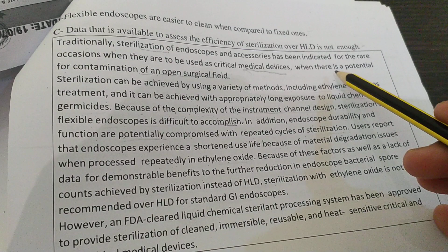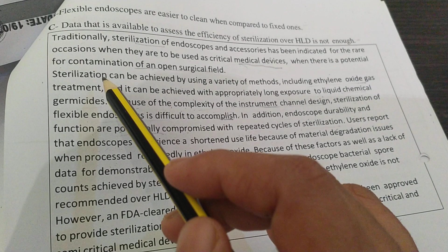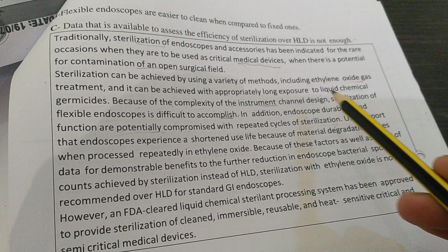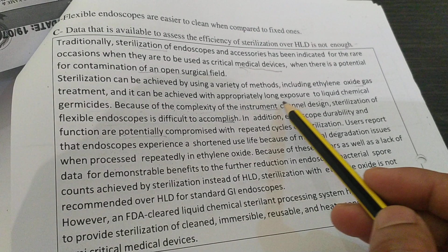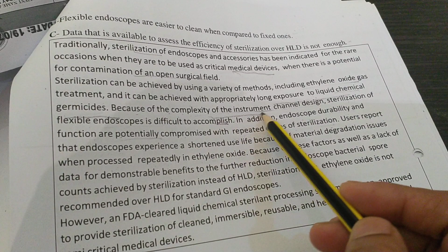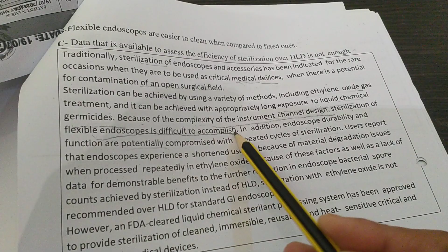It's a big extract. Traditionally, sterilization of endoscopes and accessories has been indicated for the rare occasions when they are to be used as a critical medical device when there is a potential for contamination of an open surgical field. Sterilization can be achieved by using a variety of methods including ethylene oxide gas treatment, and it can be achieved with appropriately long exposure to liquid chemical germicides. Because of the complexity of the instrument channel design, sterilization of flexible endoscope is difficult to accomplish.